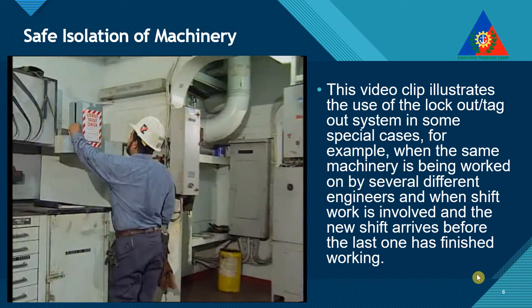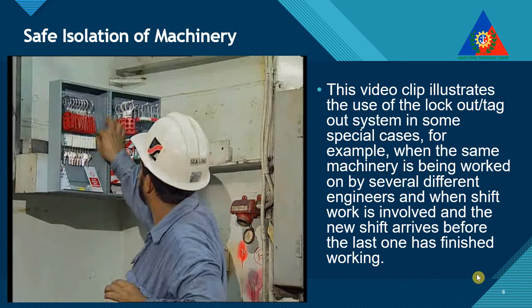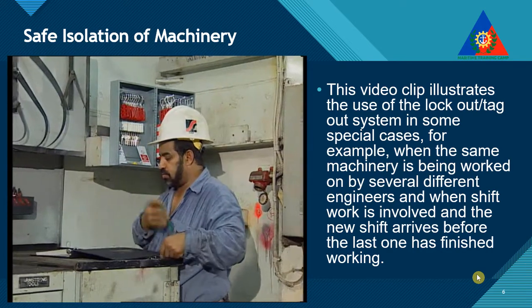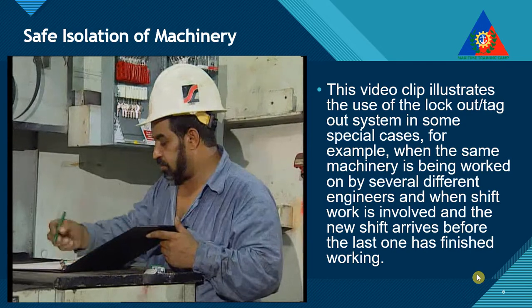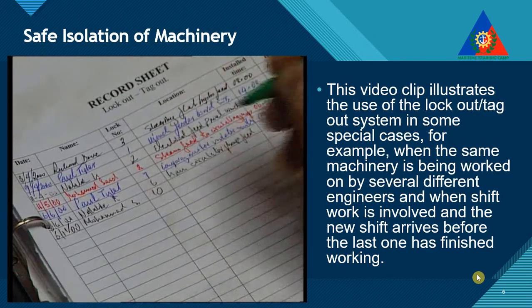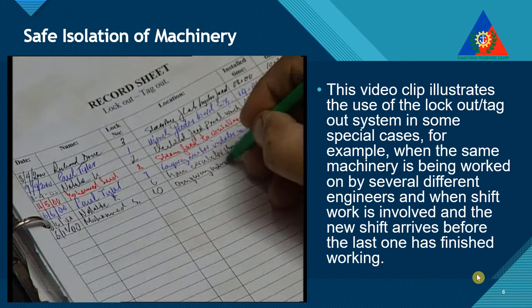Now, let's illustrate how the system works in particular situations. The right lockout device must be selected for each application, and in accordance with the company's safety management system. The number of the lock and its details must be entered into the lockout-tagout record sheet. The record sheet identifies the equipment being worked on, the identification numbers of all locking devices and tags used, where they are located, and who applied them.